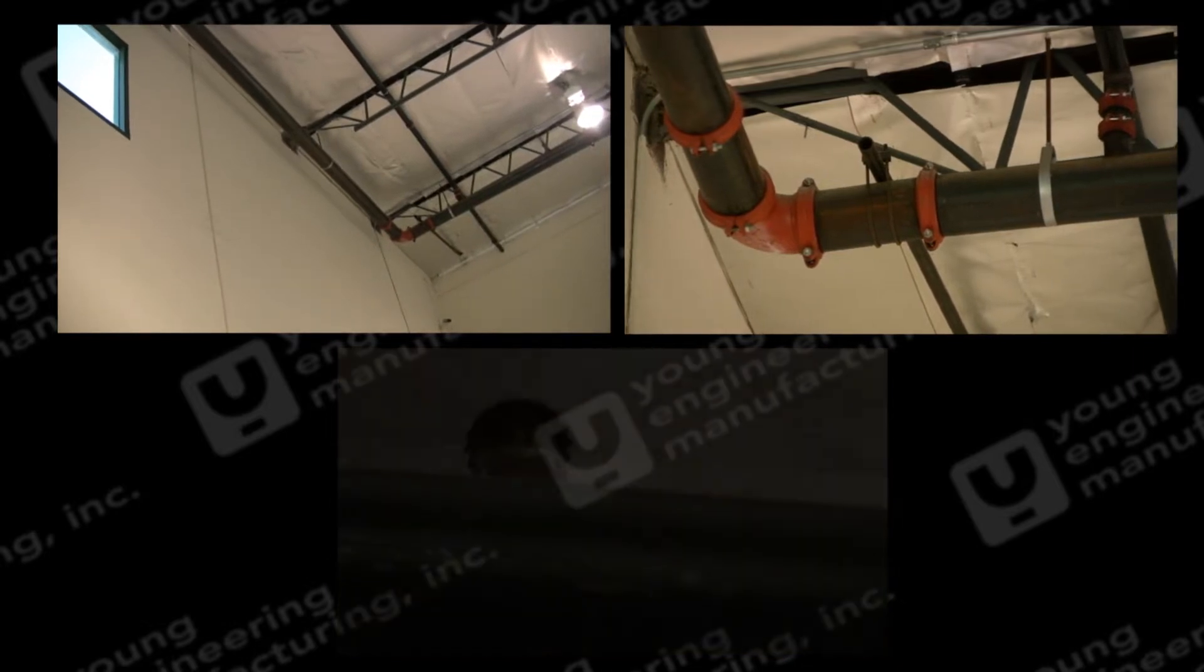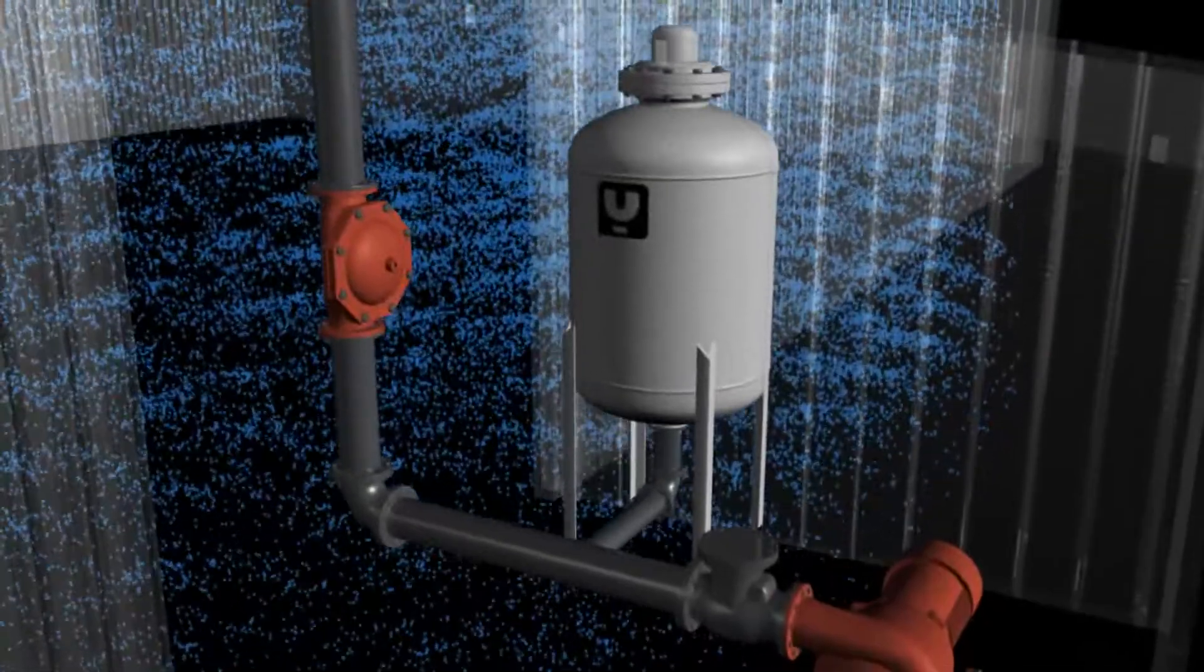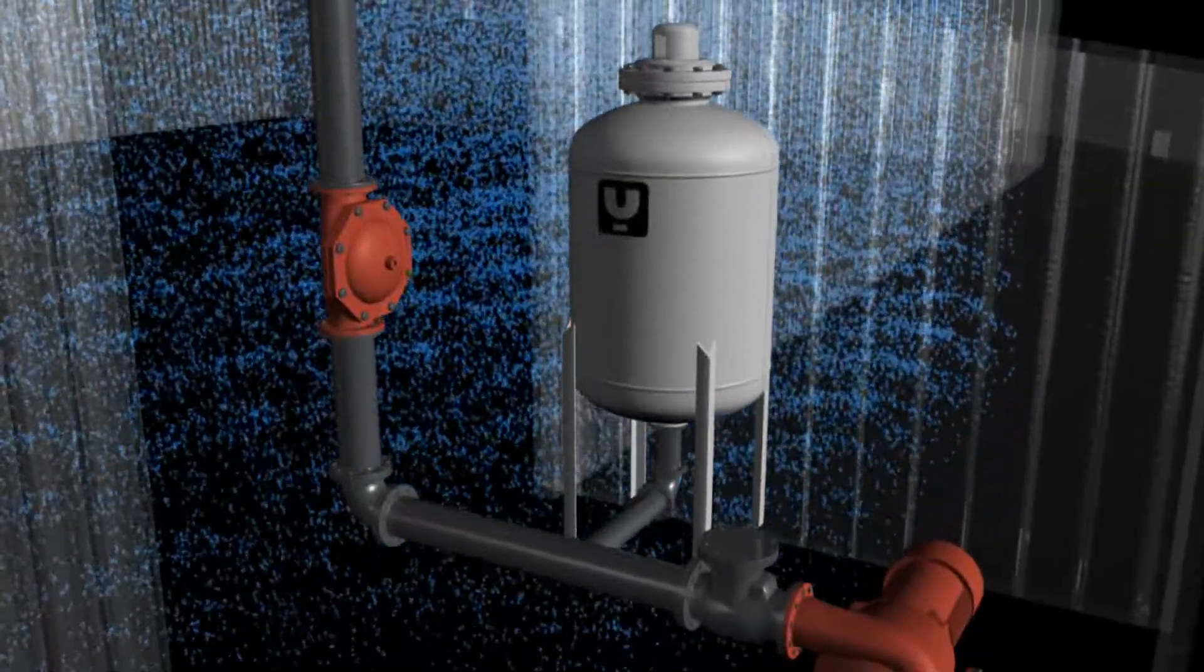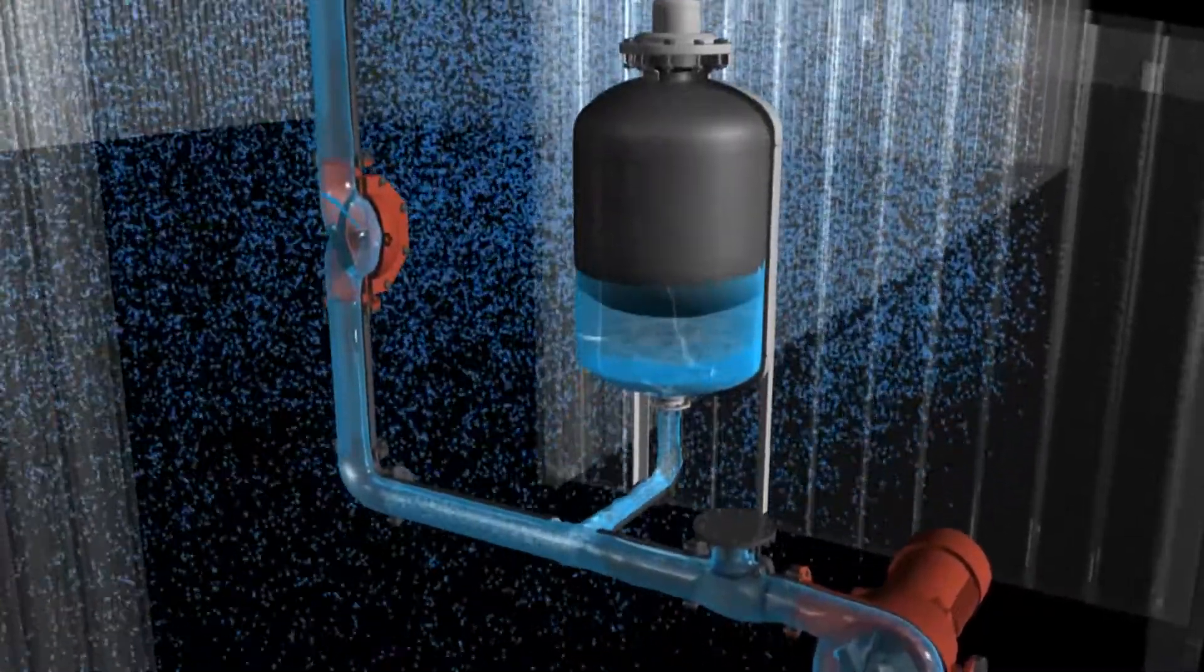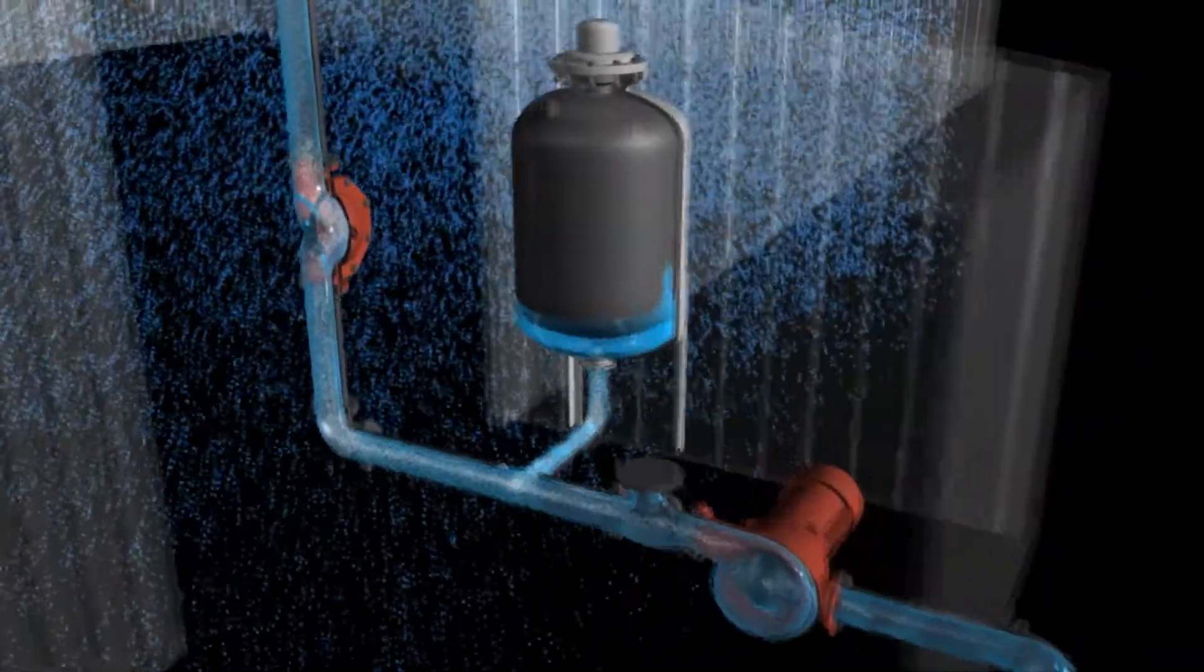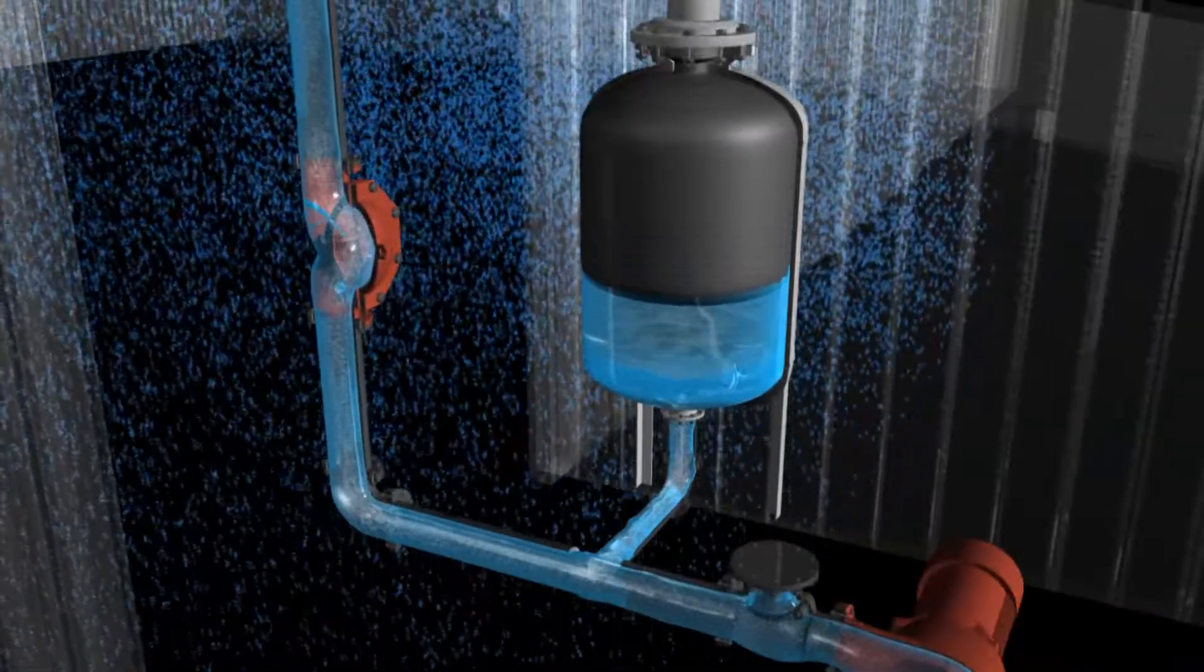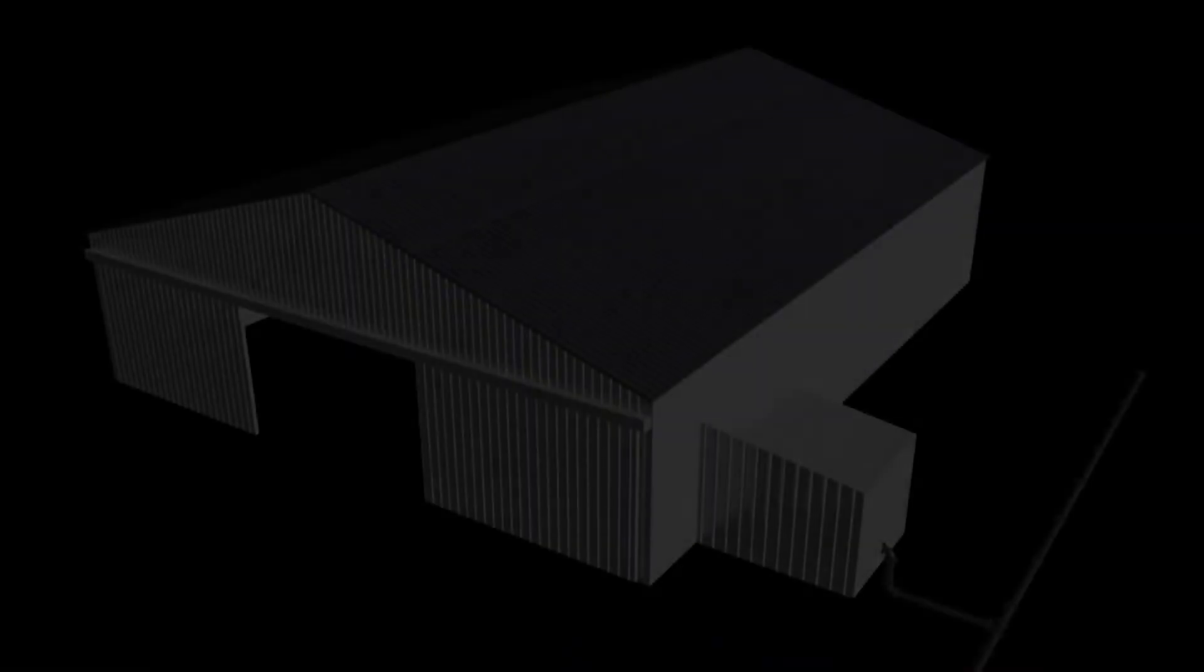After the deluge valve opens, a bladder surge tank is located in the system to provide water into the pipeline, preventing column separation. When the pump starts to provide more pressure, water is directed back into the bladder surge tank to prevent a surge condition from the pump startup.